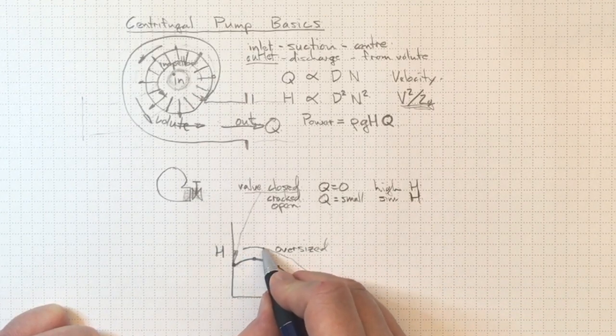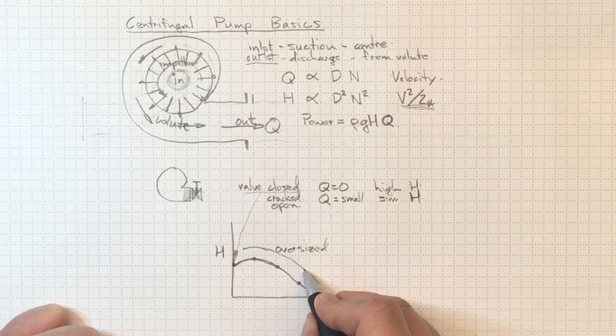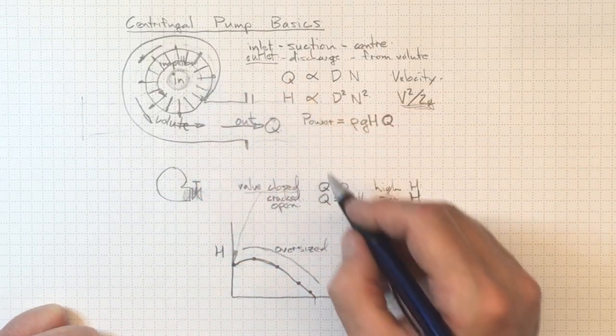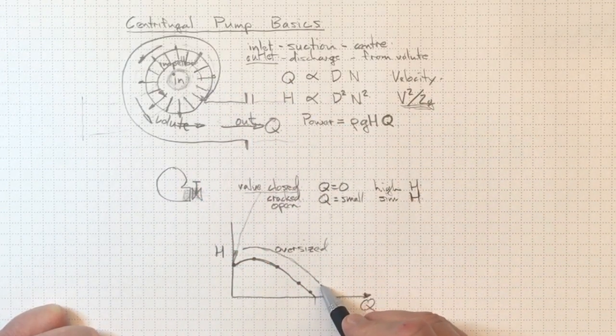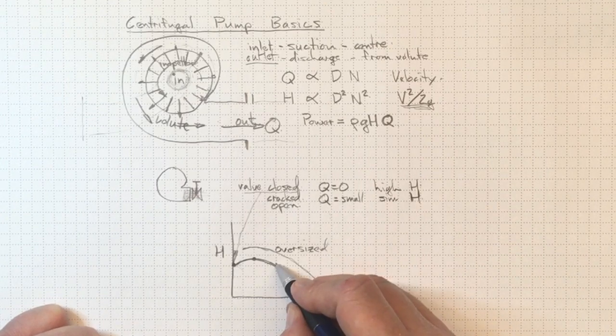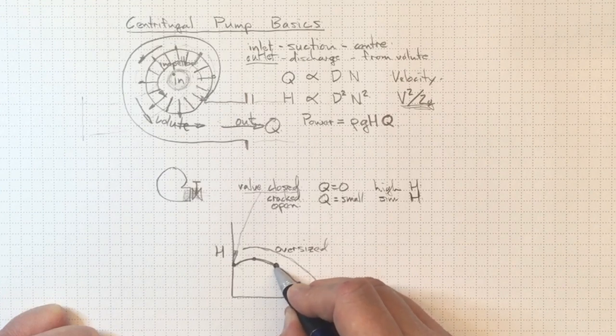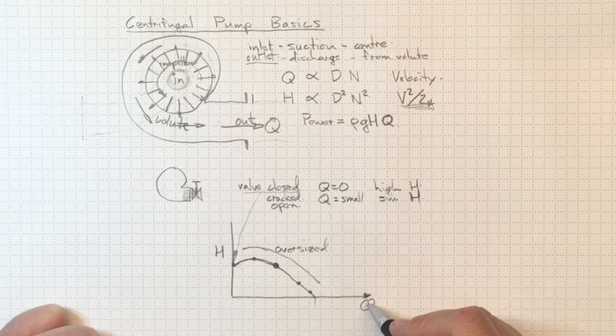So that's not going to be necessarily ideal. But it is a way of getting some more flow out of this pump by just increasing the impeller diameter a little bit. So our perfect best design, that might be the most efficient operating point here. That might be the best operating for this pump.